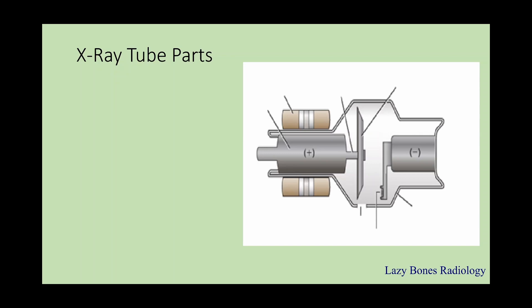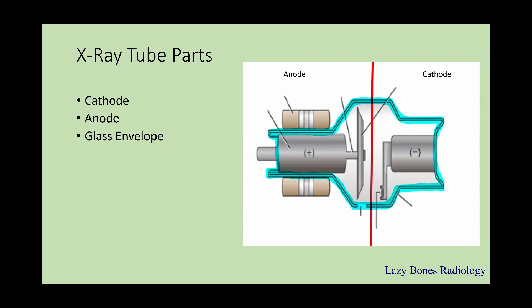Now let's begin with the x-ray tube. As you can see here, this is an image of an x-ray tube. While I was learning how to remember the parts, I used to draw a line in between them. The reason I like to draw a line in between the tube is because I like to separate the two main parts: the cathode, which is the negative side of the x-ray tube, and the anode, which is the positive side. Do not mix these up. Surrounding the cathode and anode is what's known as a glass envelope, which helps structure the x-ray tube and also maintain a vacuum within the tube.